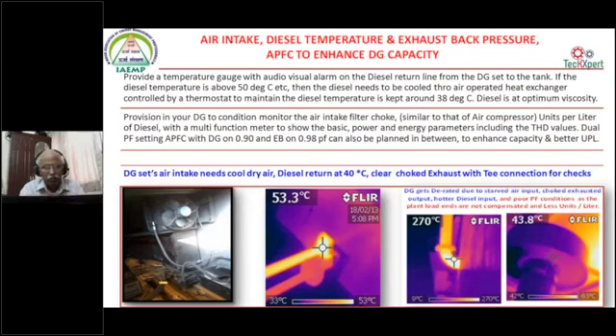to the fuller capacity. The third point is, as I was telling for the air compressor, the generator's air intake filter also gets totally choked. The generator also needs a cool dry air, which definitely needs to be provided.